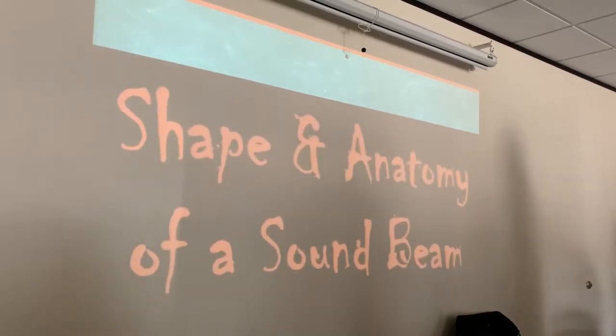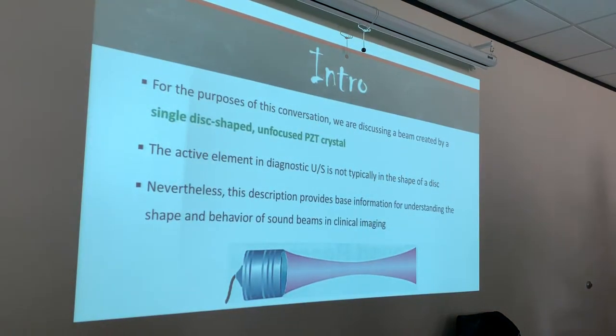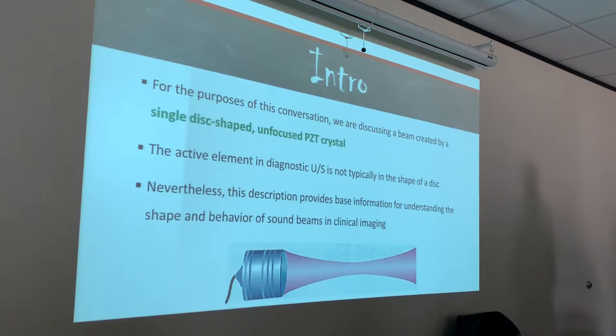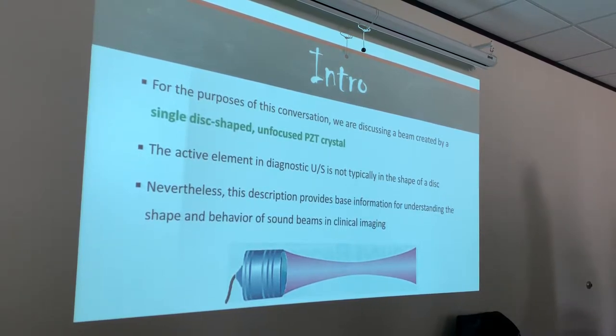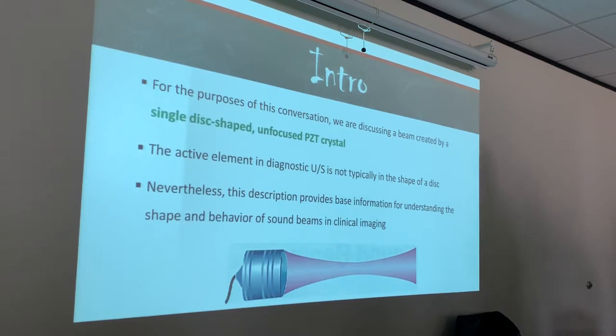Let's talk about the shape and anatomy of a sound beam, guys. When we scan with our ultrasound transducers, they are not single crystal PZT elements within our transducers. But for the ease of understanding, we're going to talk about this from the aspect of a single disc-shaped, unfocused PZT crystal. Because back in the day, before you could actually adjust that focus, the focus used to be standard — only related to the transducer diameter and the frequency.